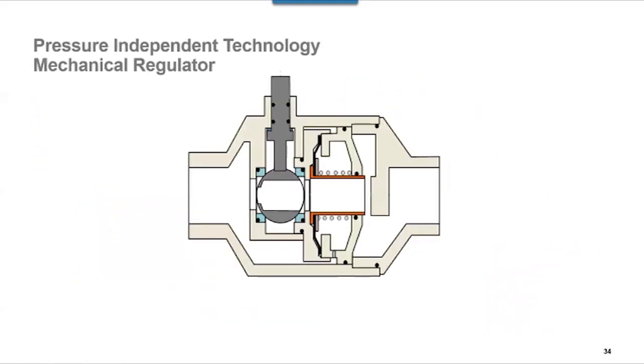Quickly, I just want to touch upon how these valves work. The mechanically regulated PI valve, simply put, flow is going to come in through the right-hand side. You notice there are 3 pressures. P1 and P3 is that differential pressure across the whole device that's required for the valve to be pressure independent. P2 is the pressure after loss going through the regulator, and P3 is the pressure after the loss going through the valve.